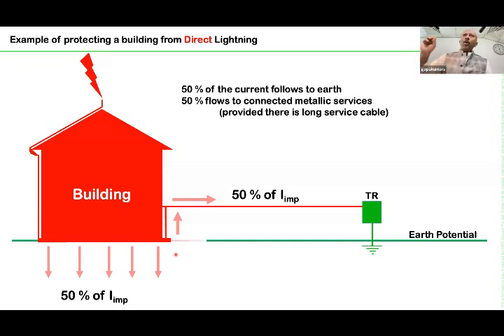Now, imagine your total lightning current is 200 kiloampere. You have a very big building, a very good building, and maybe for the entire building you have chosen the highest level of protection, 200 kiloampere. Then the rating of the SPD is 100 kiloampere, because 50% of the current is getting diverted, so you need this kind of big SPD. But imagine you didn't go for the highest lightning protection. You have gone for level 3 protection, 100 kiloampere. So with 100 kiloampere protection, 50% is only 50 kiloampere. You don't need to go for this big SPD. You can go for the small one.